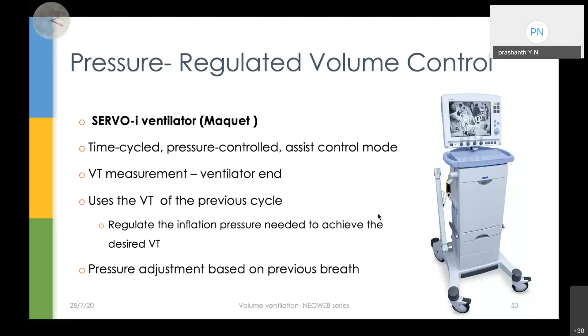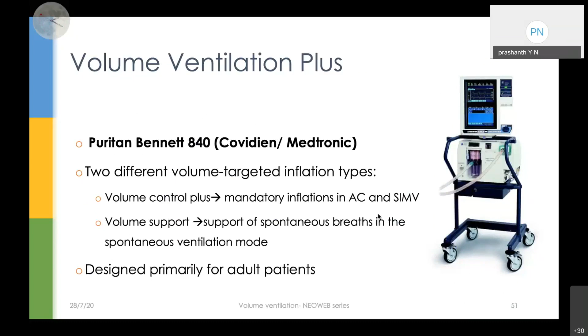So Bennett 840 also has a volume targeted mode. It actually gives two different volume targets. One is volume control plus, where it gives mandatory inflations in assist control as well as SIMV mode of ventilation. And it also gives another mode called volume support, where it supports spontaneous breaths in the spontaneous ventilation mode. But actually it is primarily designed for adult patients. I'm not aware if we can use it for newborn babies. I'm sure they must have some modifications for newborn babies also.